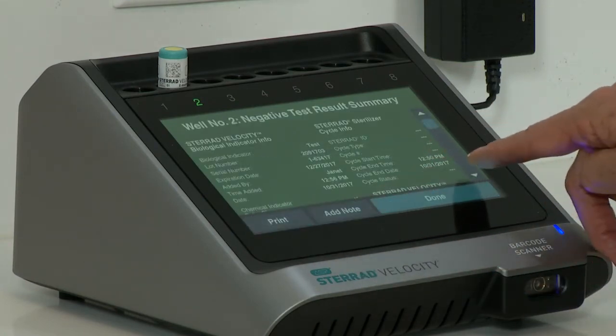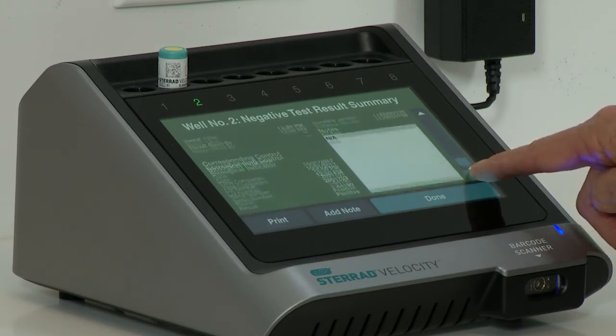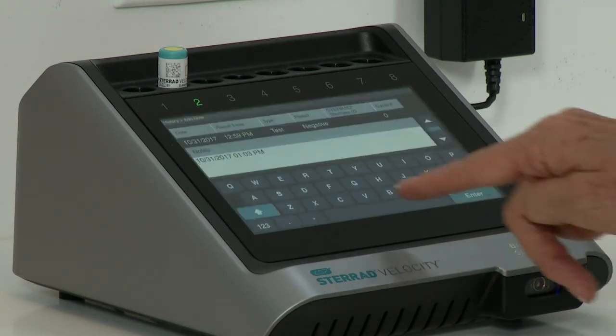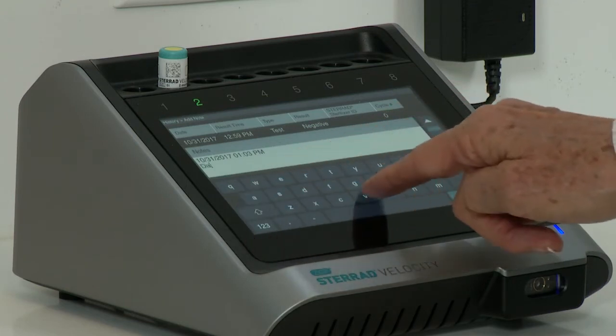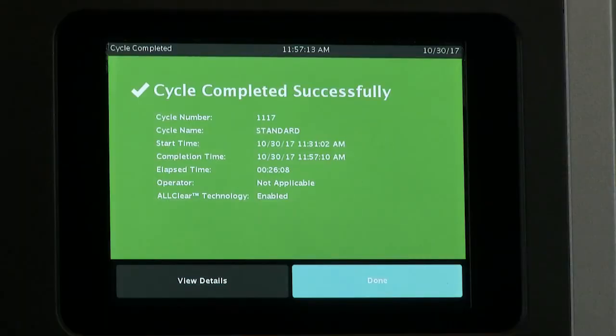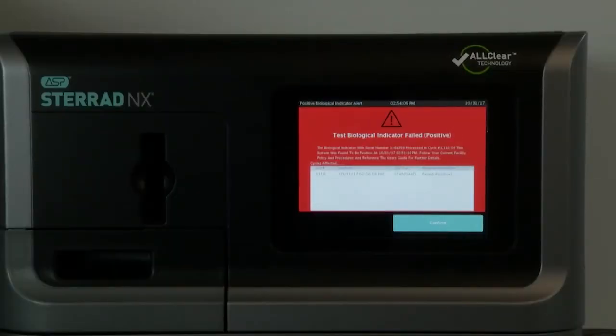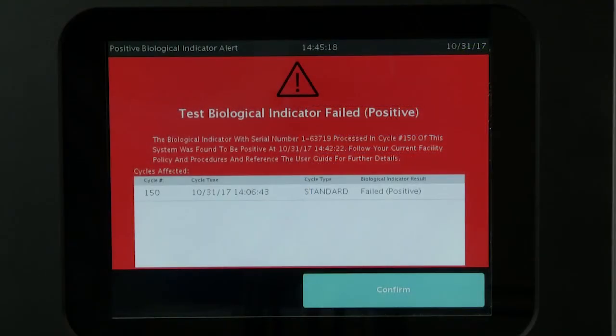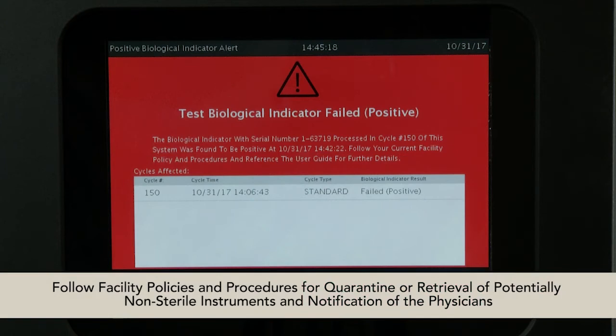For detailed information on interpretation of results, please review the instructions for use included with a biological indicator and the STERRAD Velocity Reader User's Guide. If your STERRAD system is integrated with the STERRAD Velocity Reader, the user will not be notified of negative test biological indicators. The sterilizer will be alerted when the STERRAD Velocity Reader detects a positive test biological indicator. Follow the current hospital or healthcare facility's policies and procedures regarding quarantine or retrieval and reprocessing of potentially non-sterile instruments and notification of the physicians.